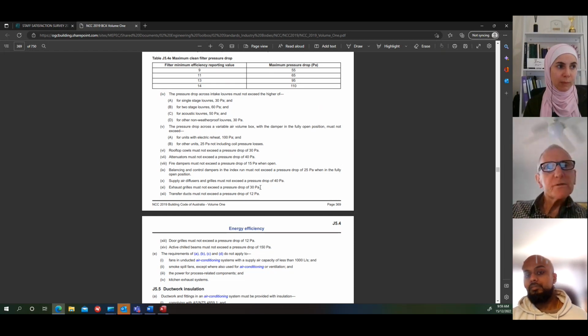I've mentioned in those notes Shape Air. You can register to access their catalogue, and it's got everything you need to look up to make a selection of a diffuser. It's worth doing a couple of times just to get a feel for what it should be, because you don't want to oversize the static too much because it affects your fan selection.